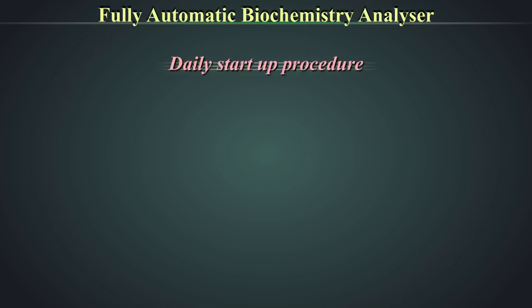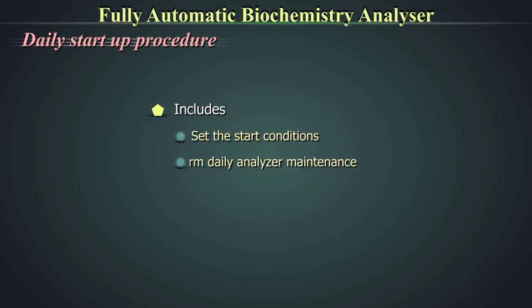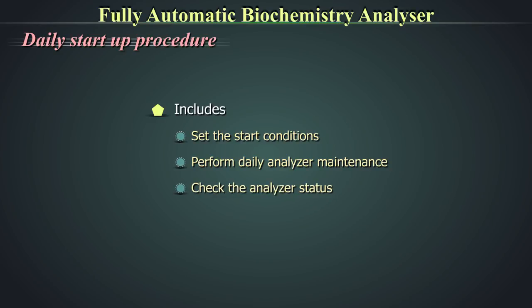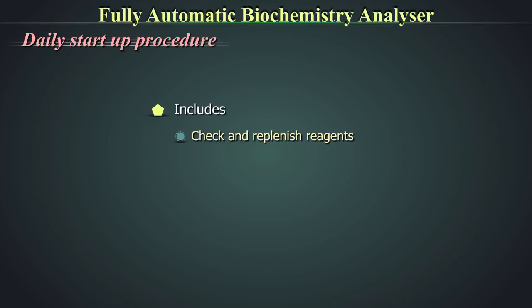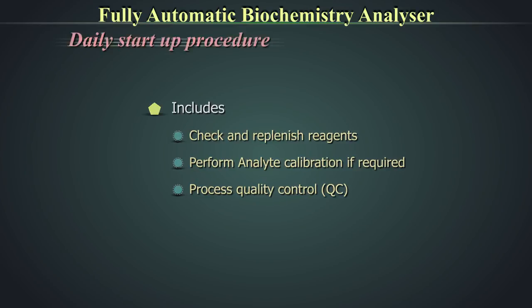Daily startup procedure. The daily startup procedure includes: set the start conditions, perform daily analyzer maintenance, check the analyzer status, check and replenish reagents, perform analyte calibration, and process quality control.